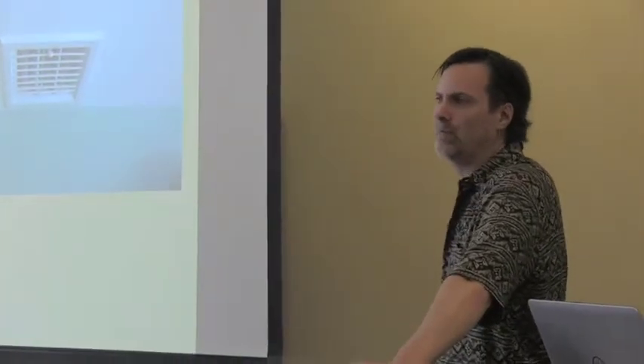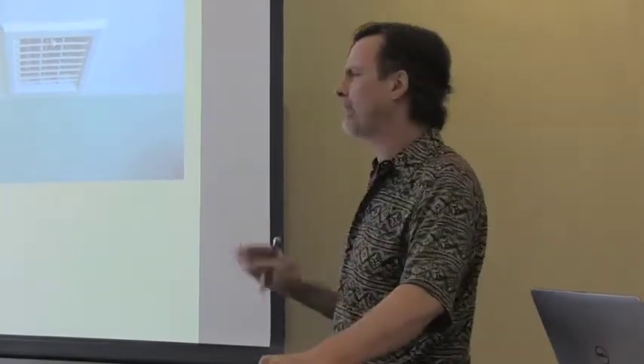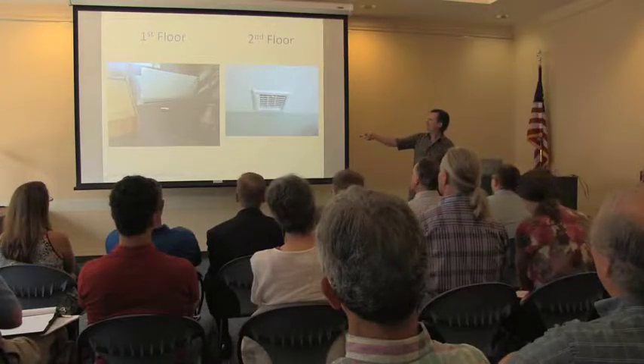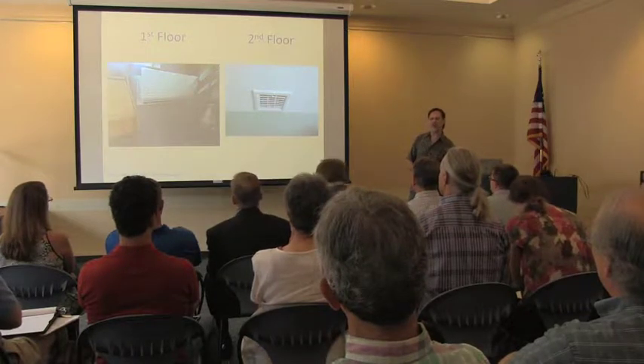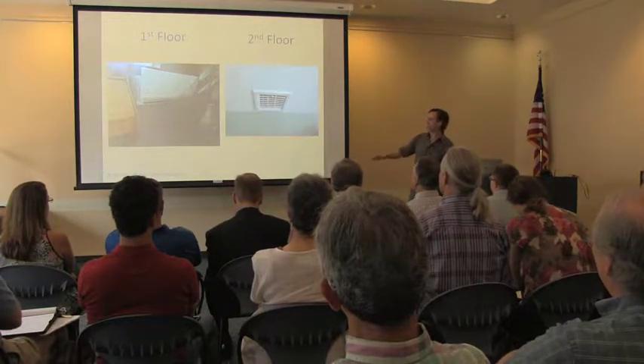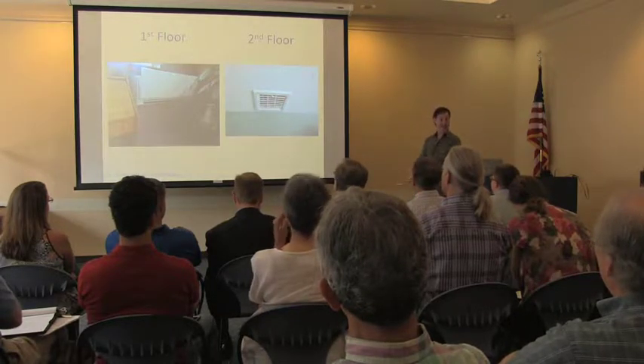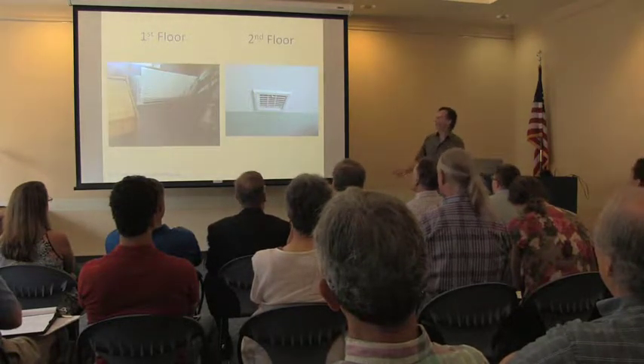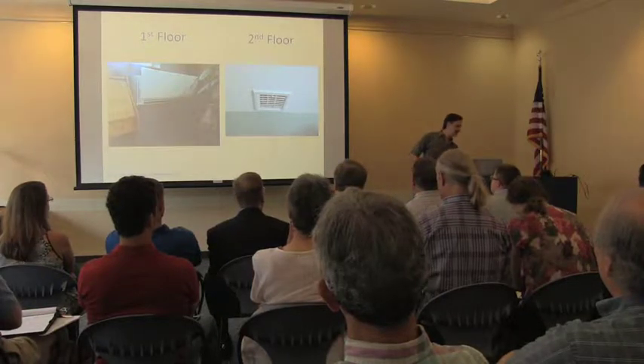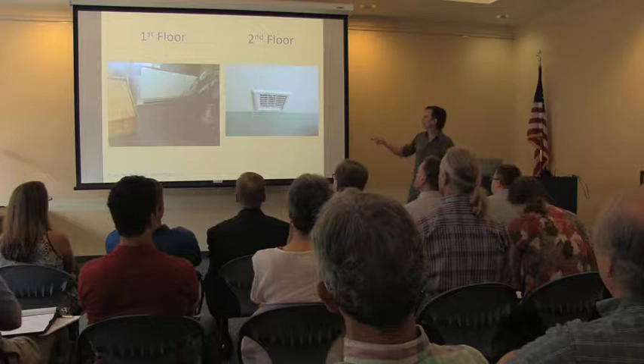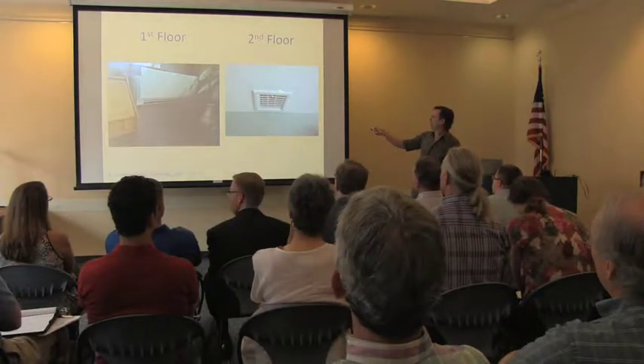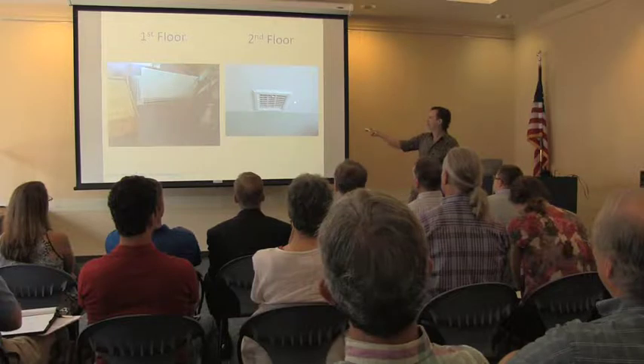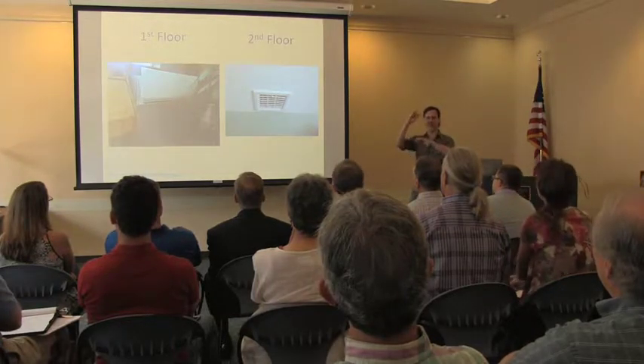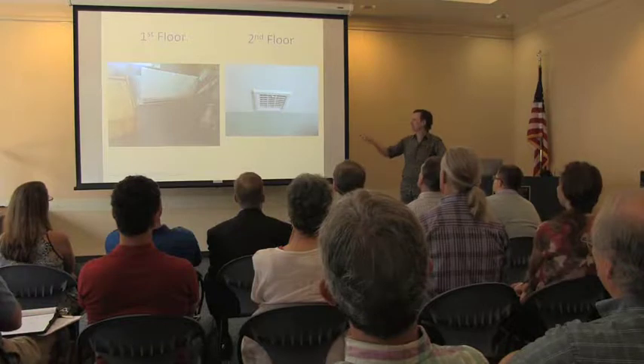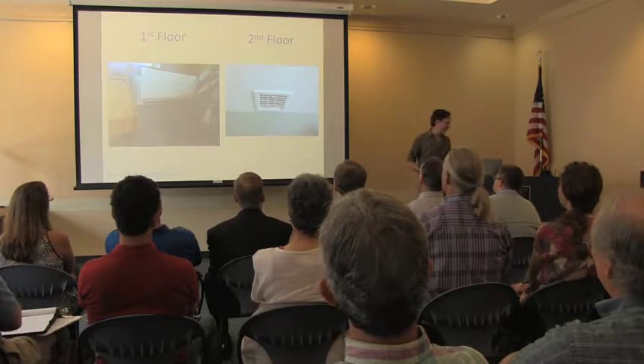That high wall application was originally designed for cooling, because that's where these things started. And they work fine for a small room, but for larger spaces, I don't necessarily recommend taking a wall unit like that that's designed for high wall mounting and putting it low on the floor, but you can put in a ducted system underneath the floor, or you can use units that are designed for that, and I've got pictures of those that come up a little bit later. In my second floor, I just have a small air handler like I showed you before, and just very conventional 8-inch by 8-inch ceiling registers in each of the three bedrooms. That works really, really well.